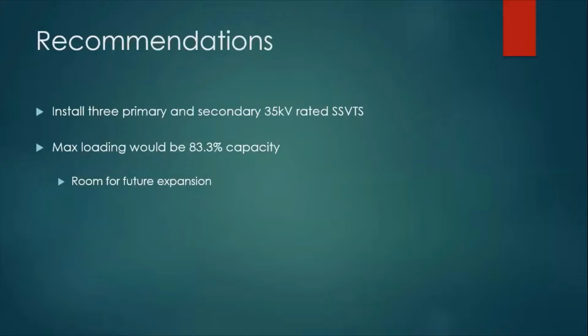While the loading was similar between the seasons of summer and winter, it was determined that under the worst case loading conditions, the summer would be the limiting factor at 29.1 kVA. Therefore, each SSVT is recommended to be rated for 35 kVA. This was selected to guarantee the substation would still be operational if all loads were connected to a single phase. If this were the case, these loads would account for 83.3% of maximum capacity of the SSVT.